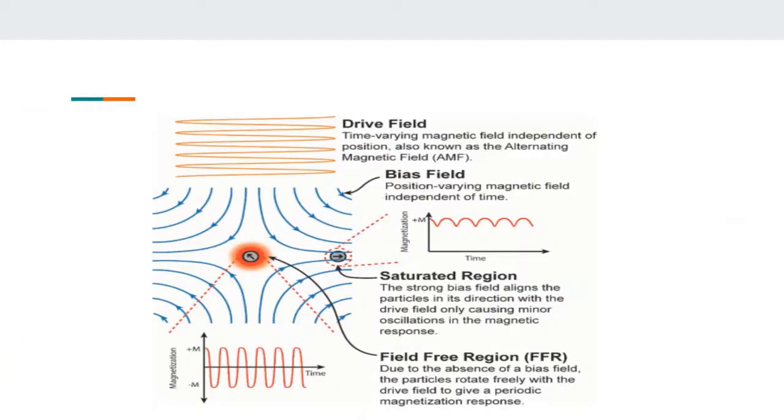The basic idea is that an SPIO tracer is injected and an AC magnetic field is applied that's called the drive field or the transmit field, and the SPIO magnetization basically follows the drive field, and then the response is detected as dM/dt by a receive coil.